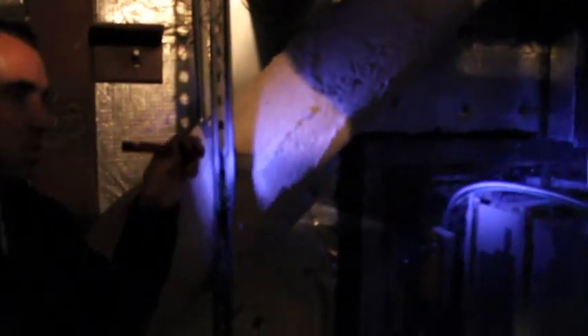So this is an example of the truss system that goes along the exterior wall. We wanted to size this duct for low velocity, 1,000 feet per minute, and what we were limited with is this existing truss system right here. So our contractors had to work together with us to make the wall penetration, as you can see right there, and then we've actually come around the existing structural steel. This duct right here, this was existing perimeter air that we had to relocate. So you could see that the duct was cut at the bottom and refed with a round duct right there.